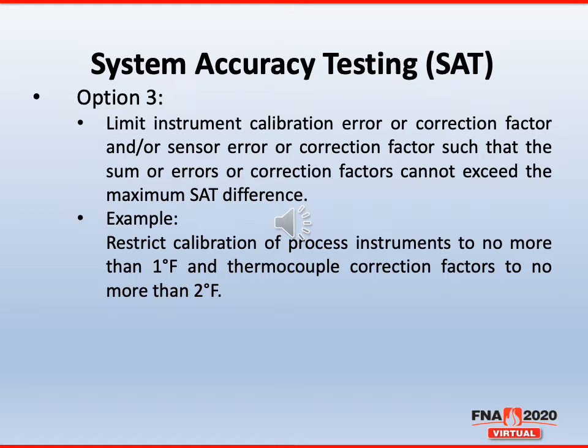For example, you restrict your calibration of your process instruments to no more than plus or minus 1 degree, and your thermocouple correction factors to no more than 2 degrees. In the worst case scenario, your tightest tolerance for an SAT for a class 2 furnace is plus or minus 3 degrees. So if you restrict your calibrations to 1 and your thermocouple correction factors to 2, add those together, they're within 3. So that is the third option when it comes to the alternate SAT process.